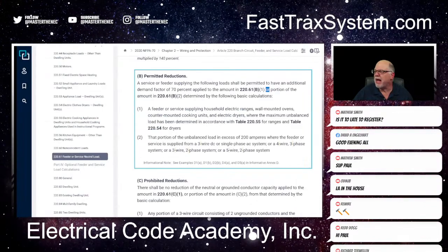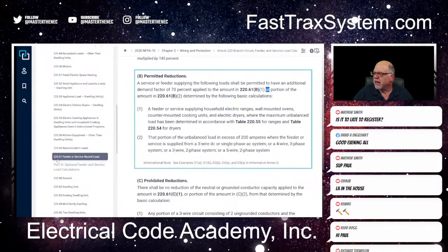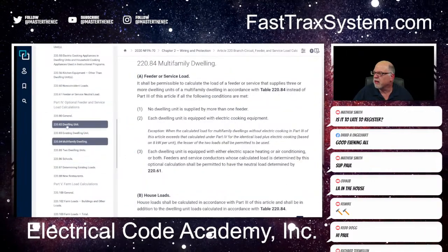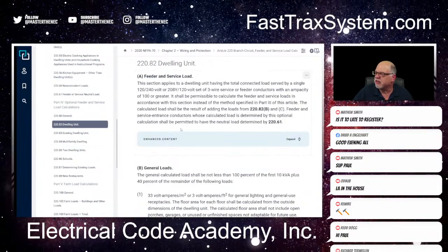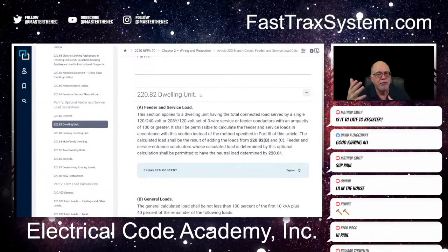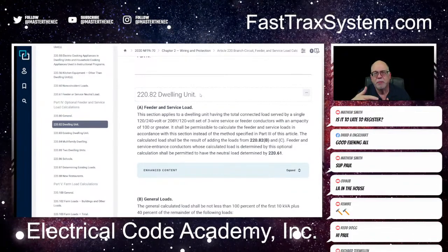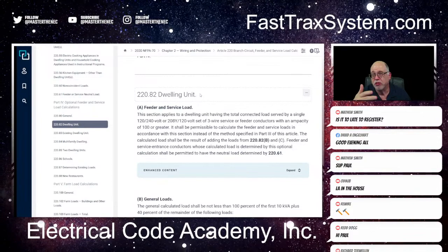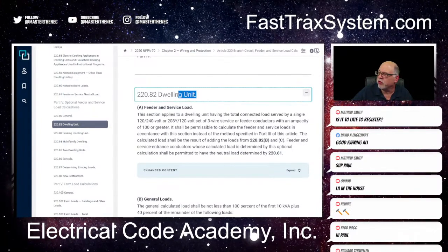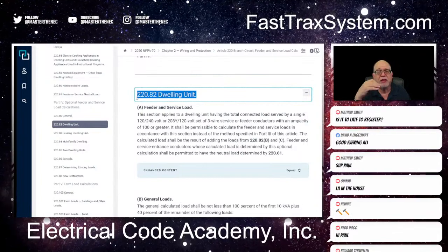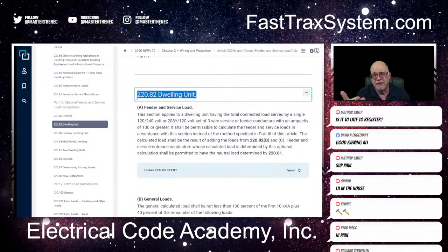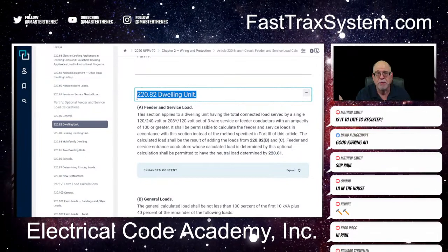So let me go back to the NEC here, and let's get down to 220. All right, so let's go to 220.82 real quick. When people ask, if you're using the optional method, what's the difference between 220.82 and 220.84? Well, 220.82 is when you're doing a calculation and using the optional method for an individual dwelling unit, which you're perfectly capable of doing.